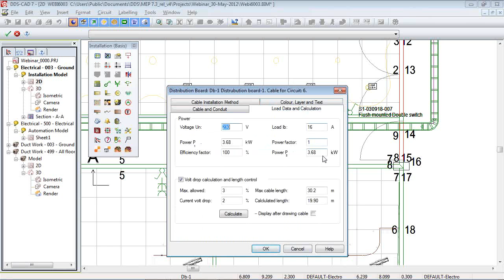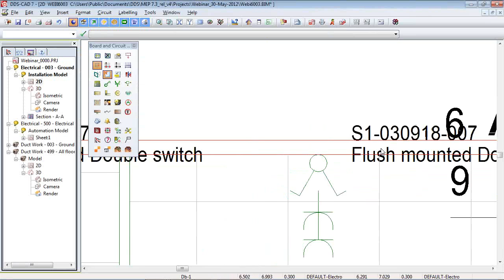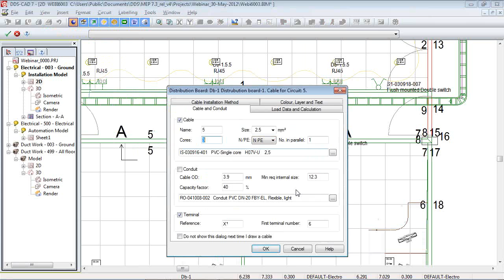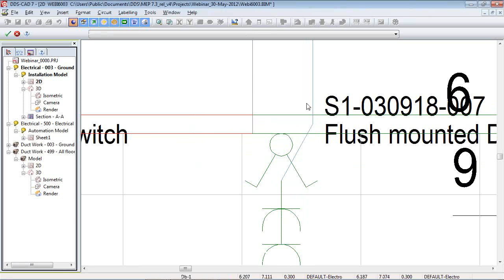We can continue on the height. Let me see. Continue cable. Okay. From this height 0.3, we can connect to the other one. And now we get an indication that the length of the cable is not sufficient anymore. So instead of increasing the diameter of the cable, I will decrease the power of the cable. So maybe we only would like to have nearly 7 amps, or we would like to have 1.6 kilowatt, and then the cable is okay again.